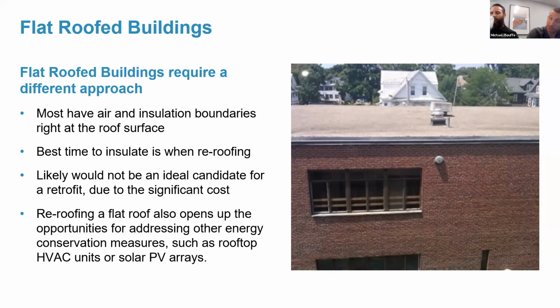Usually the time to improve your roof insulation is when you actually have to replace the roof itself. So it might not be an ideal candidate for a retrofit, but for example, if we were going to put a heat pump system in, which is going to be covered in more detail later in the presentation, you might have to replace the roof as part of a significant or extensive HVAC overhaul. At that time it would obviously make sense to improve upon the existing insulation. So there's some opportunity there, but it can be a little bit trickier to address in a retrofit application than a building with a traditional attic space.